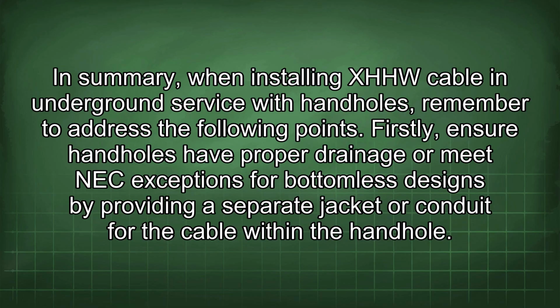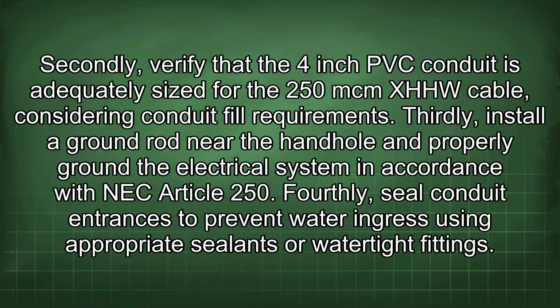In summary, when installing XHHW cable in underground service with handholes, remember to address the following points. Firstly, ensure handholes have proper drainage or meet NEC exceptions for bottomless designs by providing a separate jacket or conduit for the cable within the handhole. Secondly, verify that the 4-inch PVC conduit is adequately sized for the 250 MCM XHHW cable, considering conduit fill requirements.